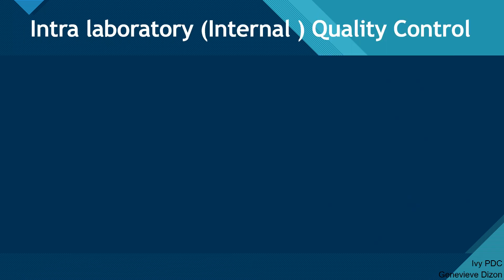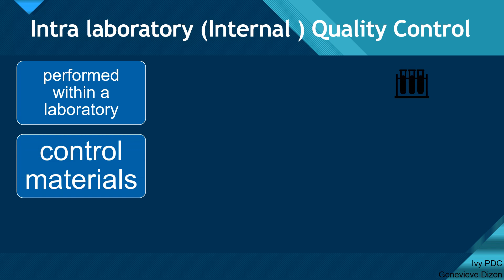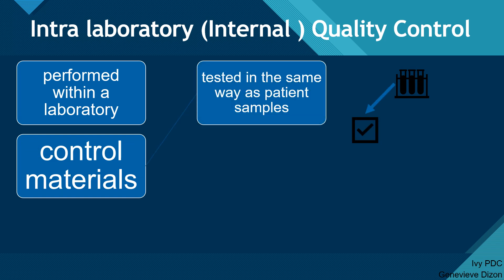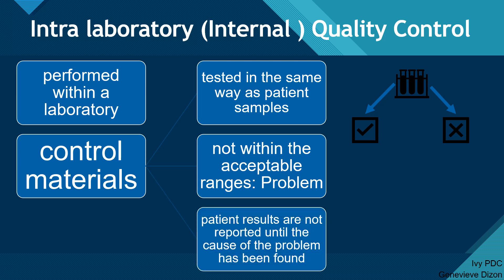Intralaboratory or internal quality control is performed within a laboratory to monitor and ensure the reliability of test results. Control materials are used to monitor the test system and are tested in the same way as patient samples to verify that quality patient test results have been attained. If the results on a control material are not within acceptable ranges, then we assume that there is a problem in the test procedure, equipment, or samples themselves. Patient results are not reported until the cause of the problem has been found and resolved, and the controls are retested to verify that everything is working normally.